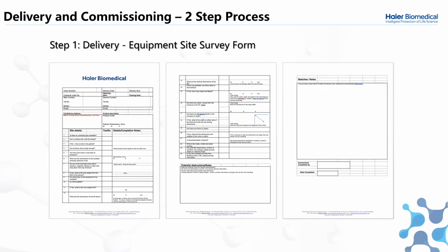This goes through very common things such as ceiling heights, if the units can be bench mounted, corners, which can be difficult to navigate for the units, as well as depth of bench, any obstructive airflow, and any other problems we may encounter during the delivery. A good site survey can affect a lot of problems down the road, and it's always important to measure twice and cut once, as deliveries can be expensive and difficult to organise.